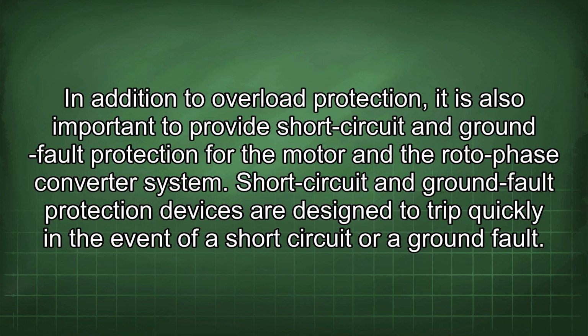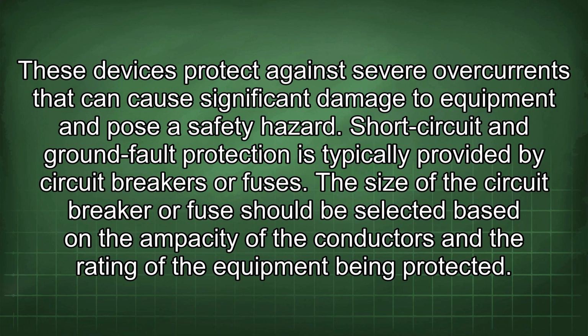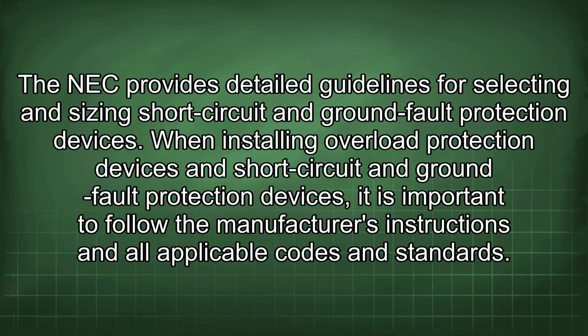In addition to overload protection, it is also important to provide short circuit and ground fault protection for the motor and the roto-phase converter system. Short circuit and ground fault protection devices are designed to trip quickly in the event of a short circuit or a ground fault. These devices protect against severe overcurrents that can cause significant damage to equipment and pose a safety hazard. Short circuit and ground fault protection is typically provided by circuit breakers or fuses. The size of the circuit breaker or fuse should be selected based on the ampacity of the conductors and the rating of the equipment being protected. The NEC provides detailed guidelines for selecting and sizing short circuit and ground fault protection devices.